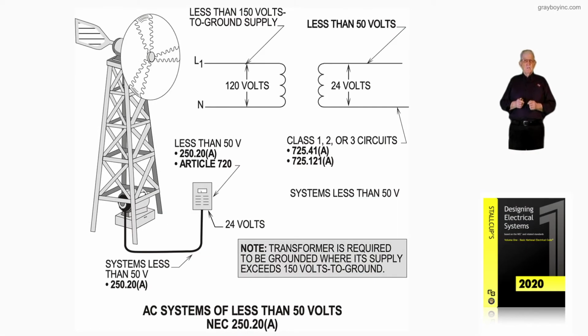Now, this illustration deals with AC systems of less than 50 volts. We just reviewed AC systems, basically of 50 volts to 1,000 volts, and 250.20(B). Now notice, again, let's look at the note first. A transformer is required to be grounded where its supply exceeds 150 volts to ground. A transformer is required to be grounded under those conditions.